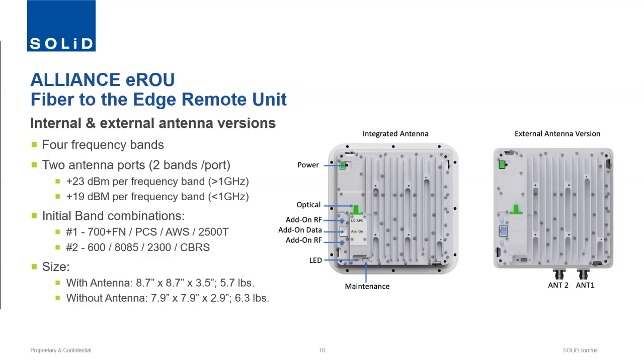Absolutely. I see a couple easy questions to answer here. One from Bill asking about the composite cables consisting of copper and fiber. I think at some point we might have created some confusion that it was fiber only, but you answered it, Kevin: it is a requirement to have some DC copper conductors pulled alongside the fiber. That can be under one sheath in a composite cable. It can also be pulled in parallel, right? And that's how I did our office: we pulled the copper conductors alongside of the fiber, pulled them together. So it wasn't separate pulls, but they were coming off separate reels.